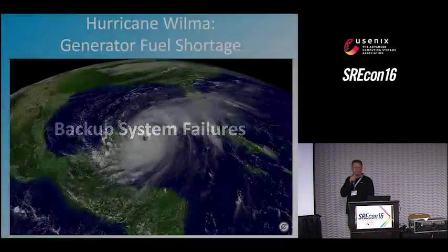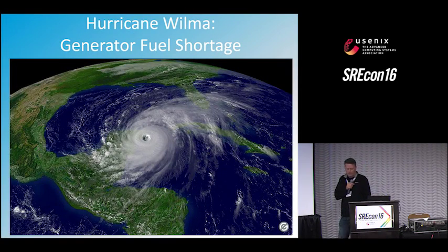But we have these wonderful backup systems, right? But they don't always work. This was a company I had my personal website hosted on in Florida, and a hurricane hit. Okay, well, that's what generators are for, right? That worked great for about 12 hours until they ran out of fuel. The problem is they couldn't get new fuel for a week because it was a disaster area.